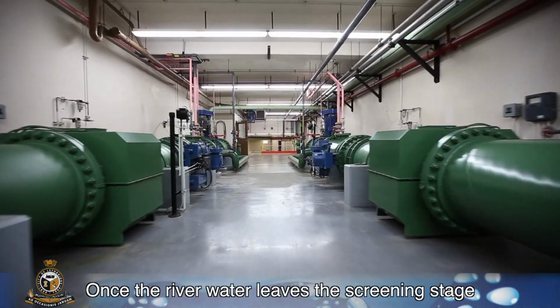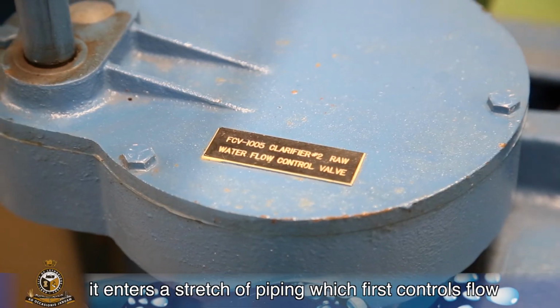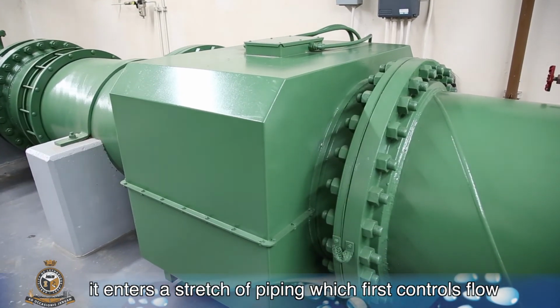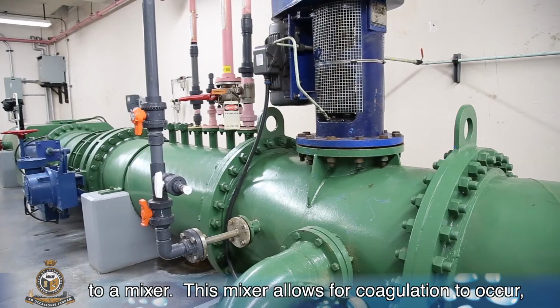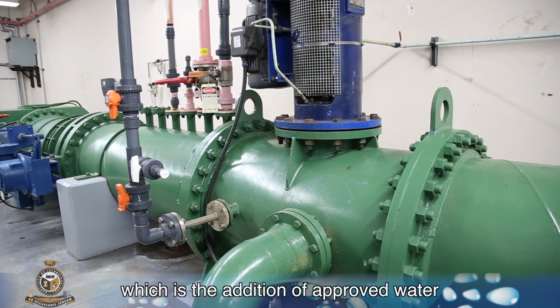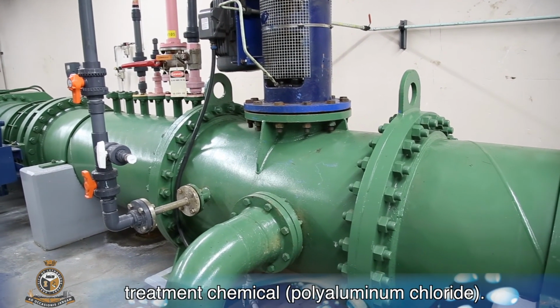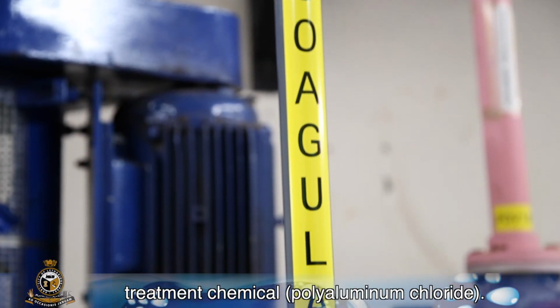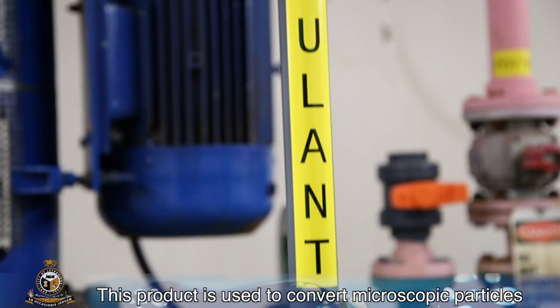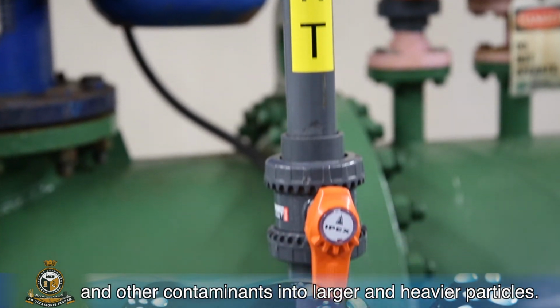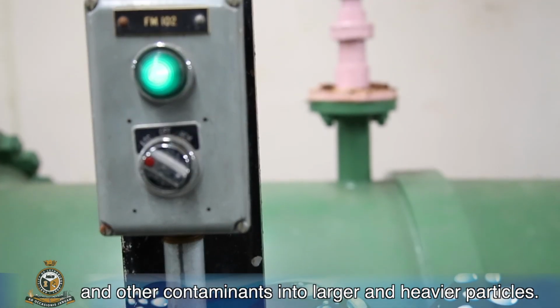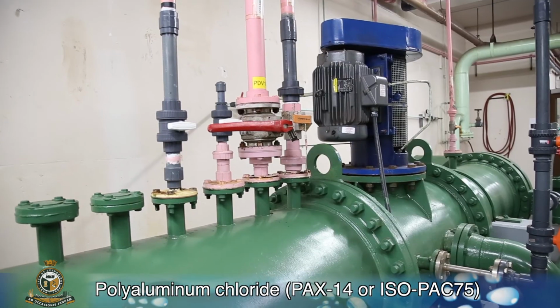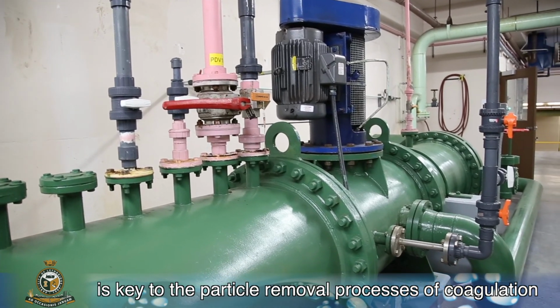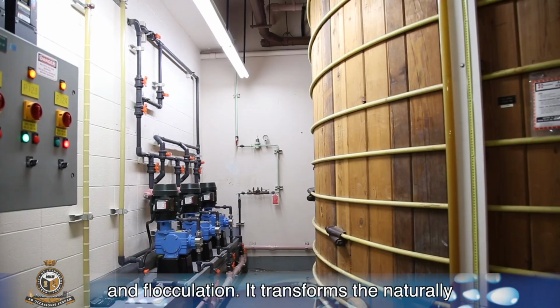Once the river water leaves the screening stage, it enters a stretch of piping, which first controls flow to a mixer. This mixer allows for coagulation to occur, which is the addition of approved water treatment chemical, polyaluminum chloride. This product is used to convert microscopic particles and other contaminants into larger and heavier particles. Polyaluminum chloride is key to the particle removal processes of coagulation and flocculation.